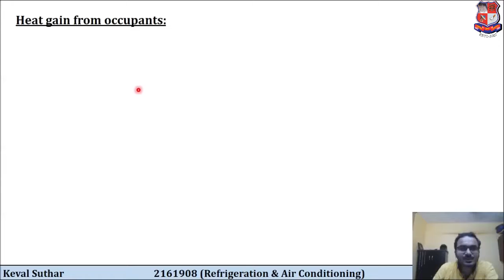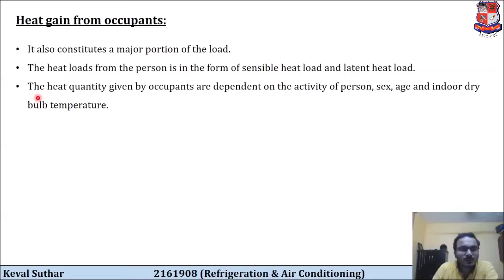Now the next is heat gain from the occupants, that is the people who are staying inside that conditioned space. It also constitutes a major portion of load. The heat load from a person is in the form of sensible heat load and latent heat load. The heat quantity given by occupants depends on the activity of the person, sex, age and indoor dry bulb temperature.